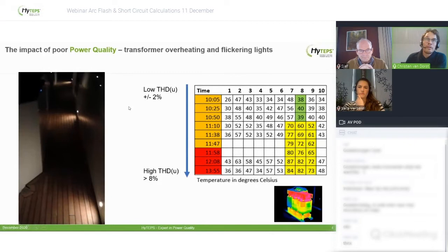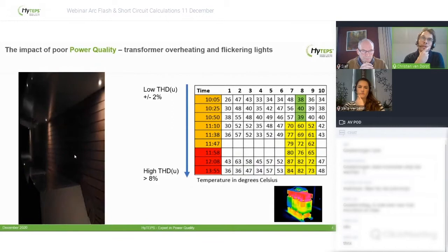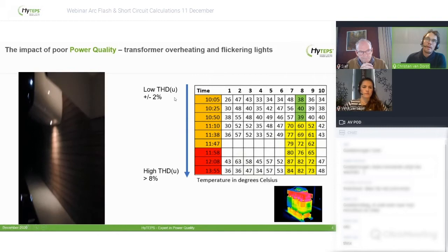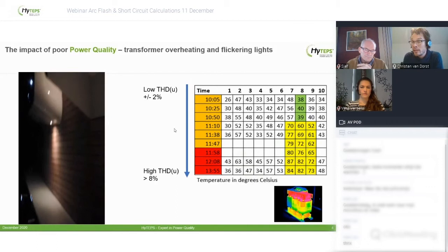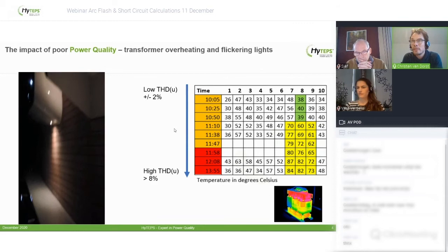The customer's complaint was flickering lights. As you can see in the video, this is on the deck of a yacht — the flickering occurred when there was very high harmonic distortion in the voltage. Apart from this, the power-supplying transformers of the lights got too hot, resulting in a fire between the ceiling and the top of the deck. There were no fire detection systems installed in this area, so there was a fire on top of the ceiling that nobody detected. Luckily, the engineer saw it in time, preventing more damage.